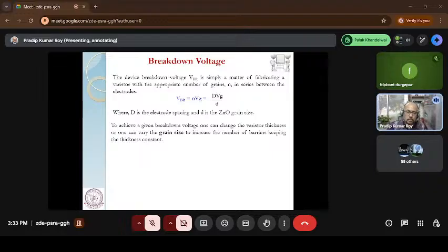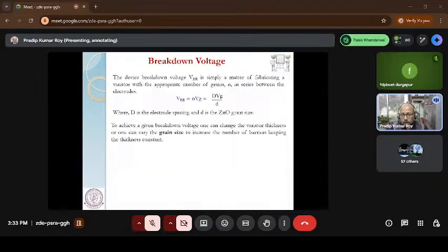For example, if you remember the D3 blocks, I worked on the D3 block. If you look at the D3 block, the diameter is 33 and the rating of the block is 3.6. Now this rating of the block depends upon the number of grain boundaries, and what voltage is required to break that grain boundary. So I said ideally all zinc oxide is coated with bismuth oxide. If I want to break one bismuth oxide layer, I need 3 volt. So if the rating of the block is 3.6 kV, that means there are 1200 grain boundaries acting as a varistor. Because to break one grain boundary I need 3 volt, if there are 1200 grain boundaries, I need 3600 volt. Then only the rating of the block comes to 3.6 kV.